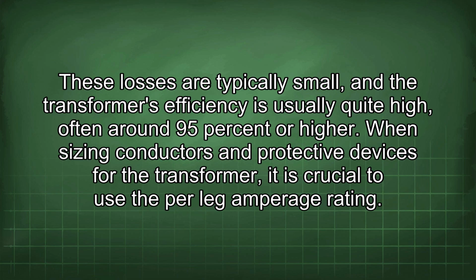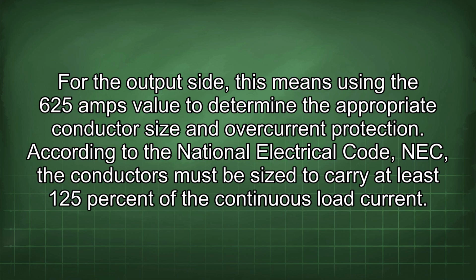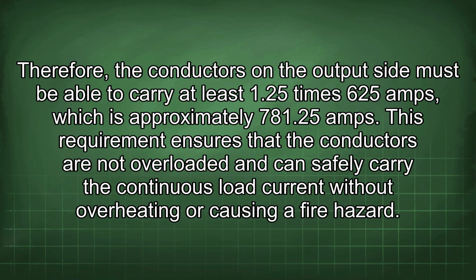When sizing conductors and protective devices for the transformer, it is crucial to use the per leg amperage rating. For the output side, this means using the 625 amps value to determine the appropriate conductor size and overcurrent protection. According to the National Electrical Code, the conductors must be sized to carry at least 125% of the continuous load current. Therefore, the conductors on the output side must be able to carry at least 1.25 times 625 amps, which is approximately 781.25 amps. This requirement ensures that the conductors are not overloaded and can safely carry the continuous load current without overheating or causing a fire hazard.